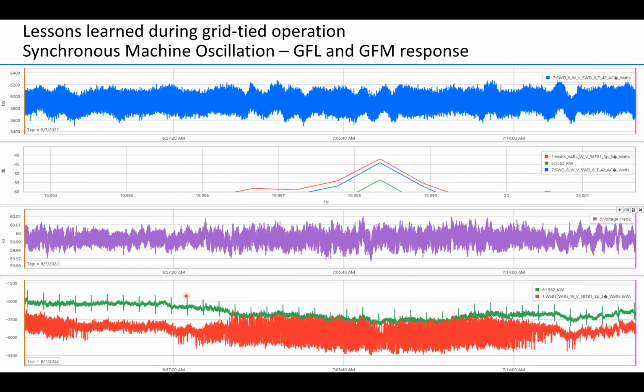Now, what you will notice here is there's a spike going on the real power on this green trend, and it's happening once every 47 or 48 seconds. That is not an expected thing to be happening. This happened quite a while ago. I forgot exactly what the driver was or what the root cause was, but we know this is not something that should be happening. But this is a good comparison of the differences between grid forming and grid following when it comes to steady state response.